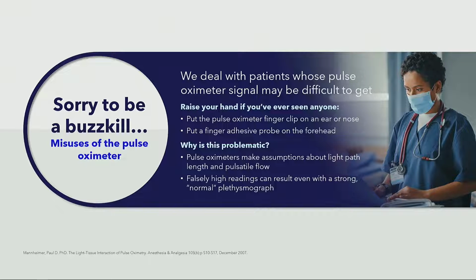This is a problem because the pulse oximeter and those calibration curves are making assumptions about the light path length, right? Because I told you that absorption of the light, some of that is just the tissue itself, and then some of that is the arterial pulsations. And the path length for a finger is very different than the path length for an ear. So it's not valid to take the sensor that's meant for one part of the body and put it on another. Another thing that kills me: even if you get a strong plethysmograph, your pulse oximeter can be wrong because of those calibration curves. So even if you put the pulse ox on a part of the body where that probe wasn't meant to go, you see that lovely waveform and you're like, yeah, I got my waveform, I can trust it. You can't necessarily trust it, even with a strong waveform.